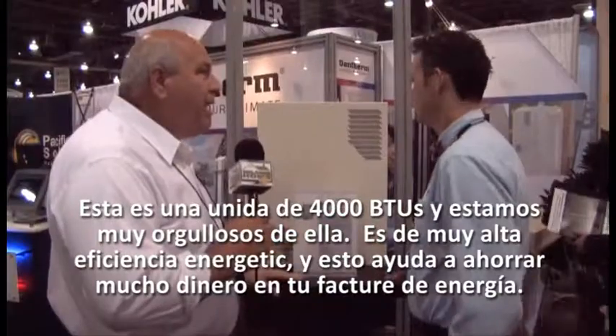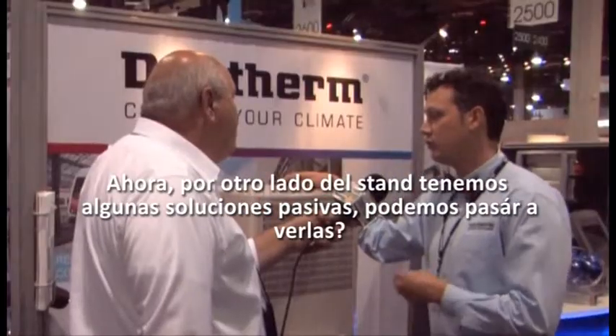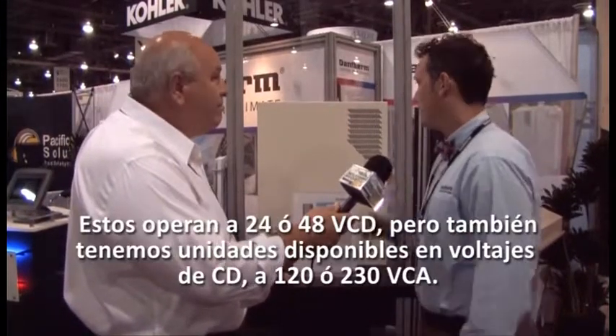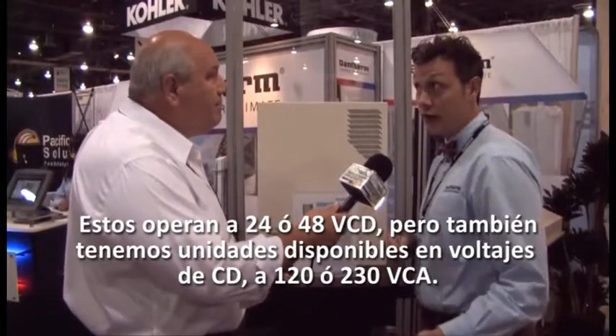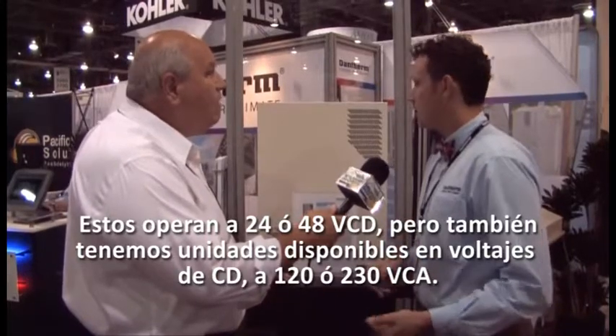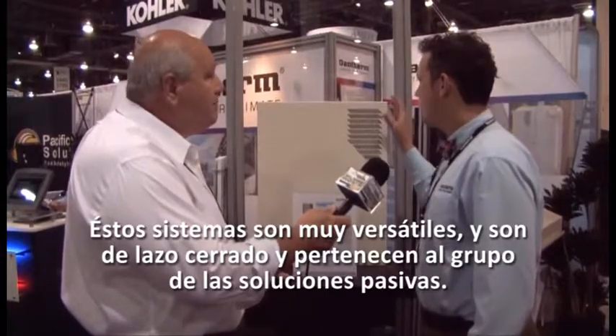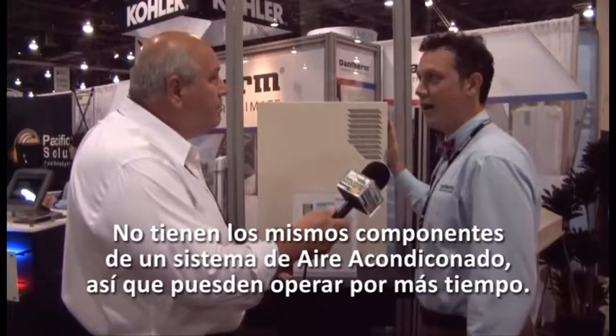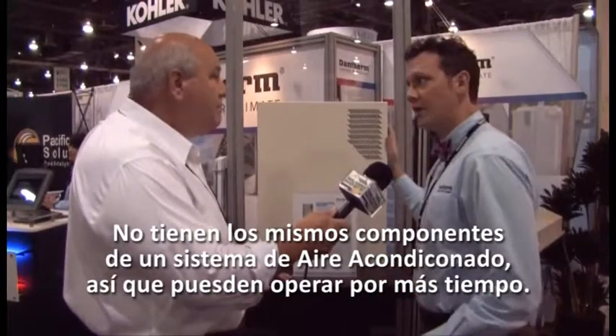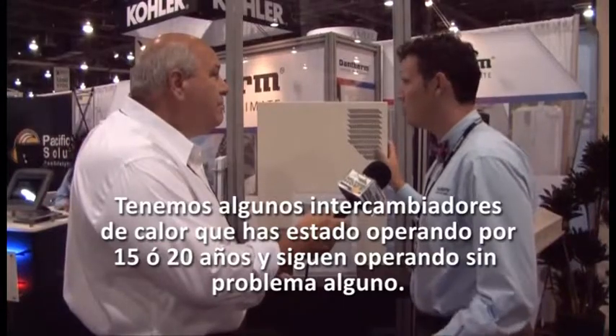Now on the other side of the aisle, let's look at some passive solutions. This is a quiet unit. Your refrigerator at home is about 55 decibels; our unit is 62. This is our heat exchanger, which really launched us into the telecommunications world, so we're very proud of it. It has an in-field rating of 10 years, running off 24 or 48 volt DC, and it's also available in AC voltages of 120 and 240. This unit is very versatile. It's closed loop and passive, meaning you can't get below ambient, but it's very efficient. It has fewer parts than an air conditioner, giving it a longer lifespan. We have heat exchangers that have been in service for 15 to 20 years and are still going.